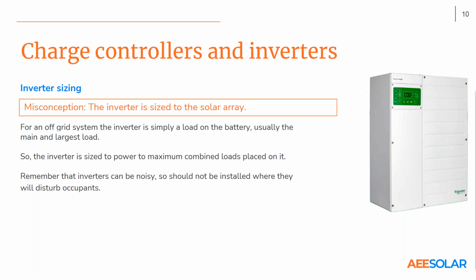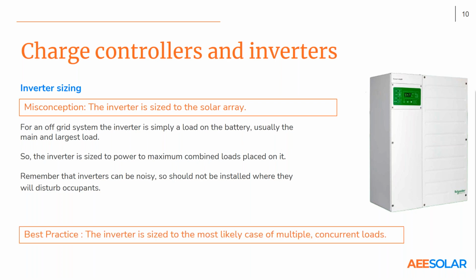Here again we have the misconception that the inverter is sized for the solar array, but in an off-grid system it's really only sized for the loads placed on it, not just the biggest or largest load, but all the loads expected to be placed on it at one time. That does mean a savvy user can control what loads they run when, and keep the size of the inverter a little smaller so it stays more efficient or less expensive.